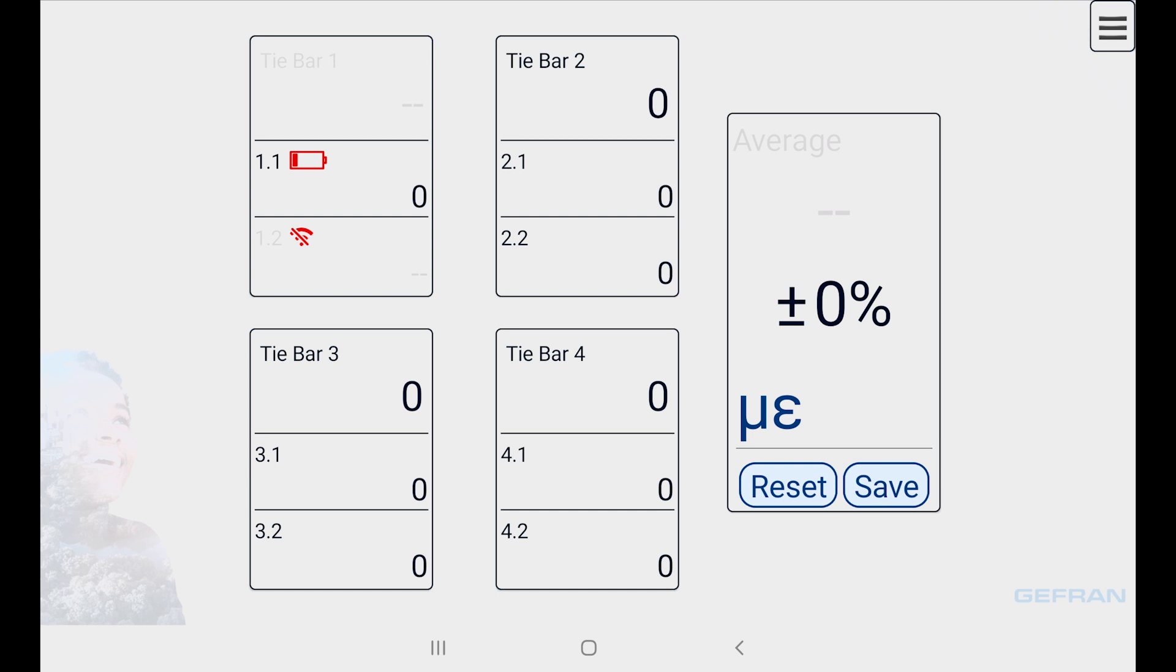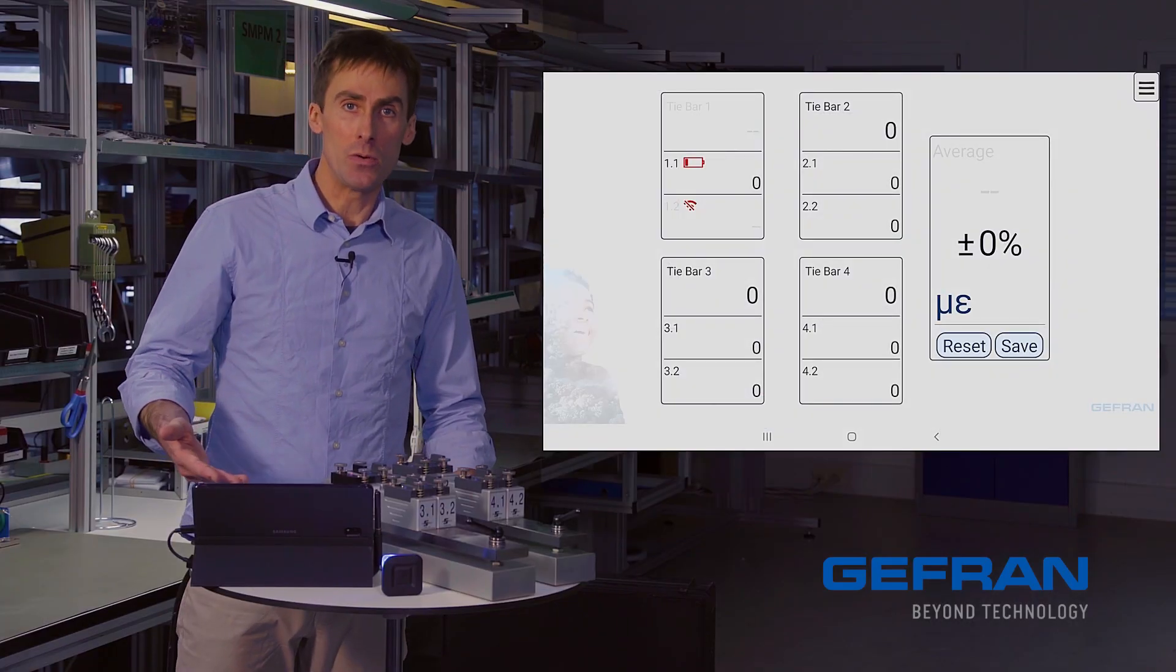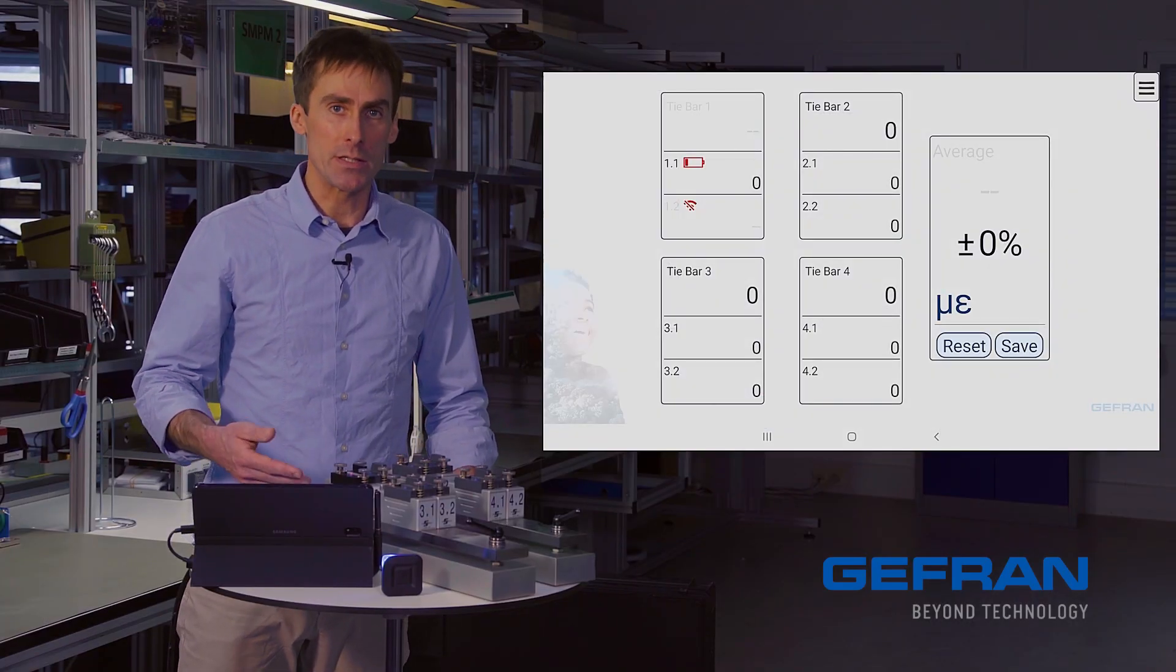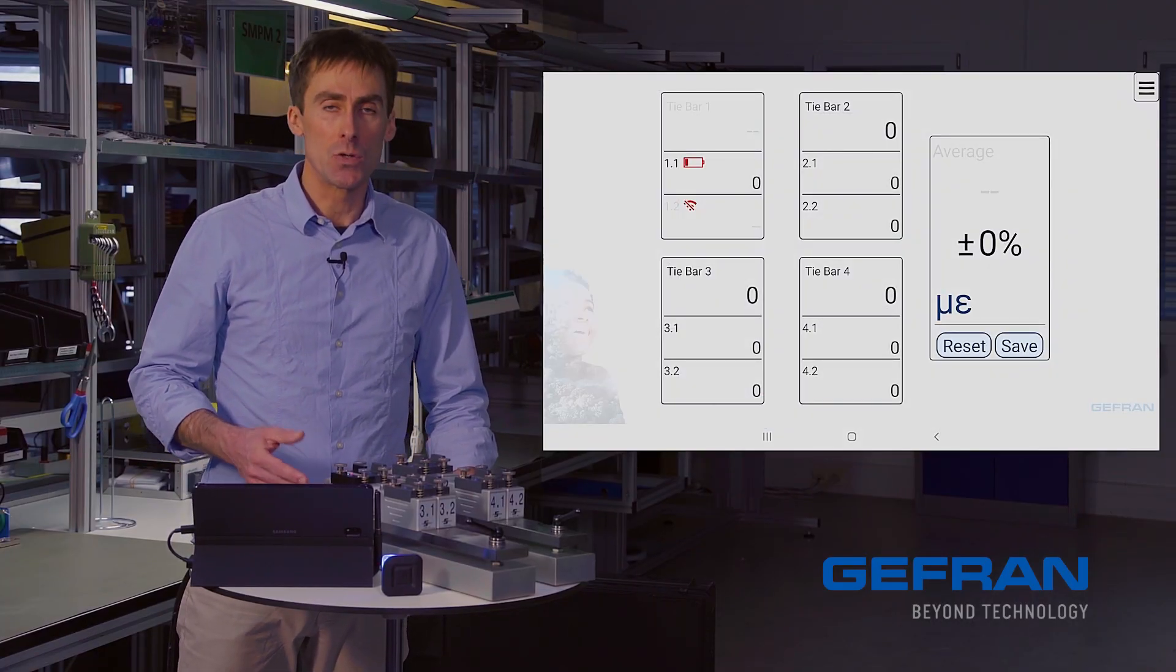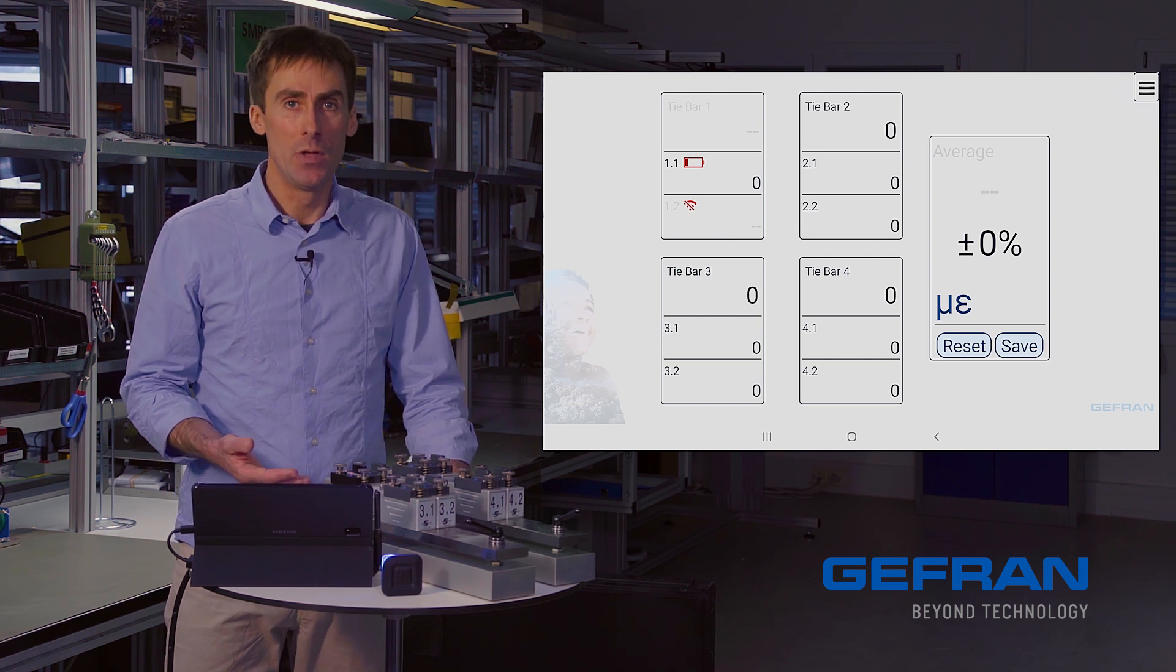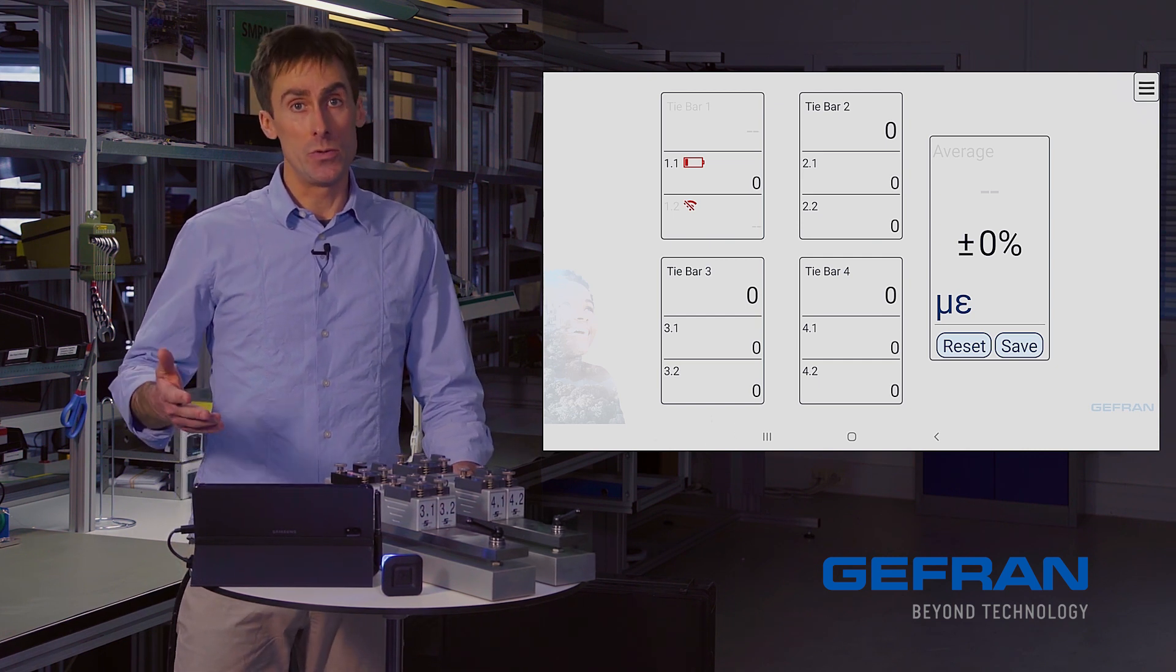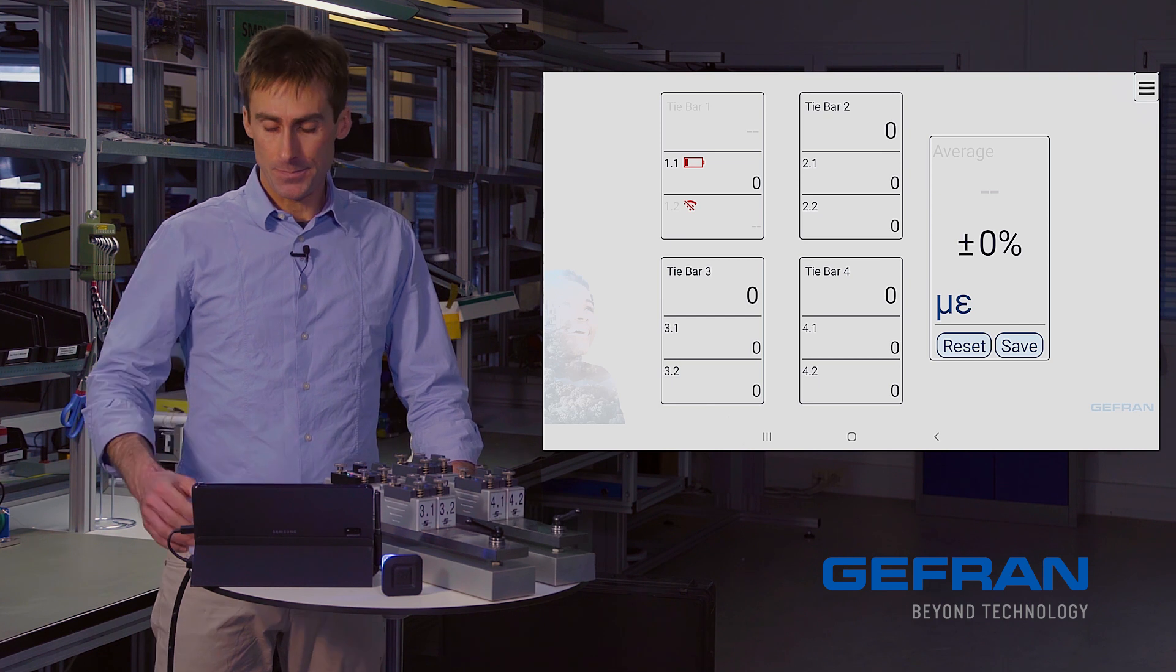And with the lost signal, we now have a placeholder, these two dashed lines in gray. Also, we've lost the signal for tie bar 1 and for the average. These things can't be computed without the missing sensor. So what do we need to do to solve this problem? We need to replace the sensor 1.2 with a new sensor.